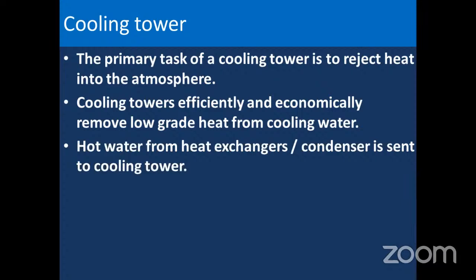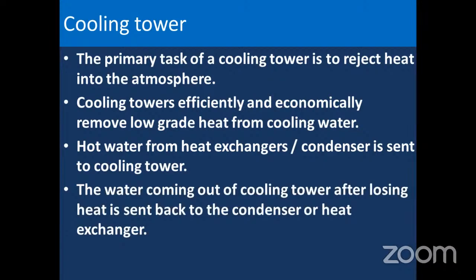Hot water from heat exchangers, condenser. Actually, in our case, we are seeing condenser. The condenser water is the cooling water after getting the heat from the steam. What is the heat it is getting, sir? It is a phase change heat, sir. Phase change heat, not a sensible heat. That's why it is of very huge quantity. Converting from steam to water requires much of cooling water. That phase change has to occur. Otherwise, thermal cycle will not occur continuously. The water coming out of cooling tower after losing its heat is sent back to the condenser or heat exchanger.